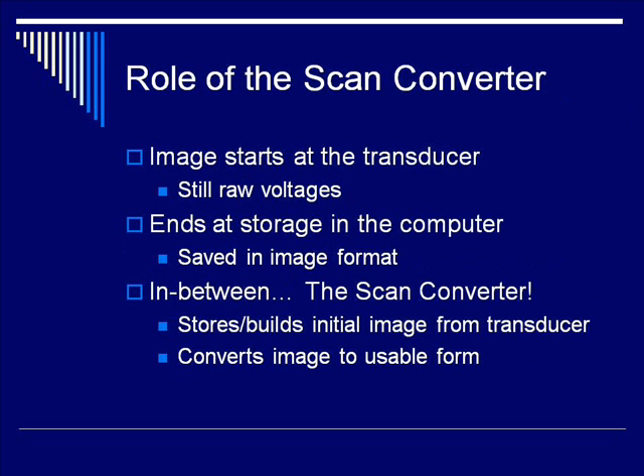We start our journey at the transducer. The transducer sends our image to the ultrasound machine — except it doesn't send a completed image. What it sends is voltages, and it sends these voltages line by line to the computer. Our journey ends at the computer, saved in an image format that you could easily read on your home computer. In between, we have the scan converter.